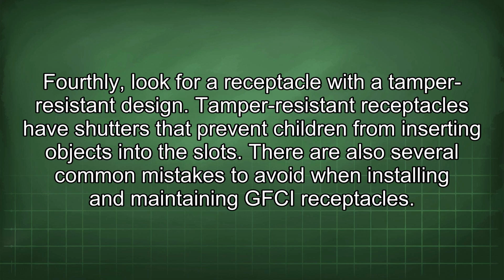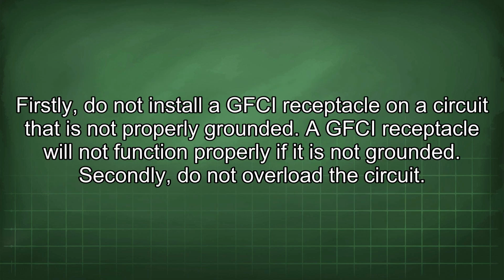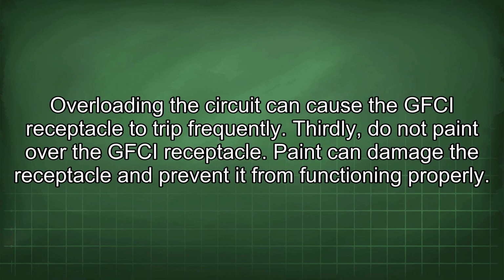There are also several common mistakes to avoid when installing and maintaining GFCI receptacles. Firstly, do not install a GFCI receptacle on a circuit that is not properly grounded. A GFCI receptacle will not function properly if it is not grounded. Secondly, do not overload the circuit. Overloading the circuit can cause the GFCI receptacle to trip frequently.